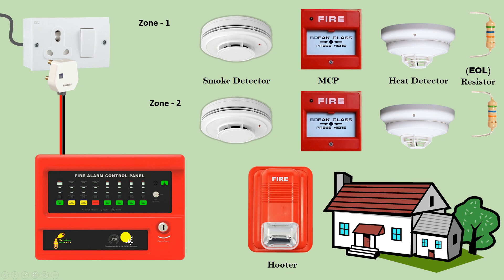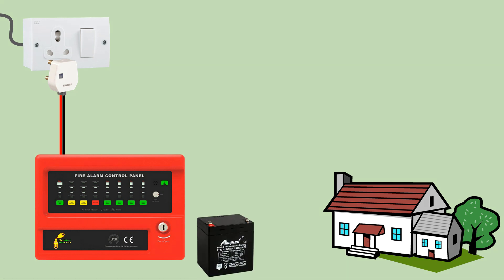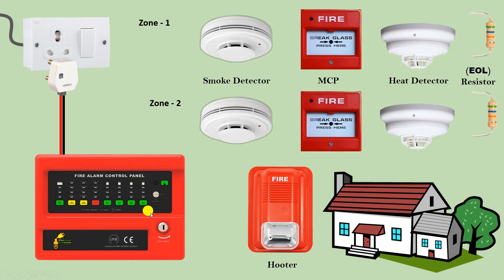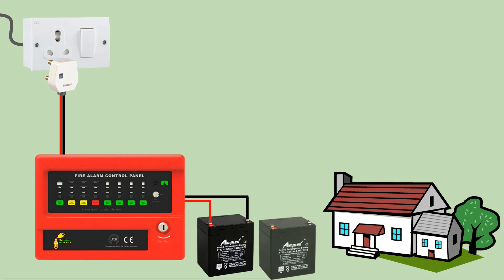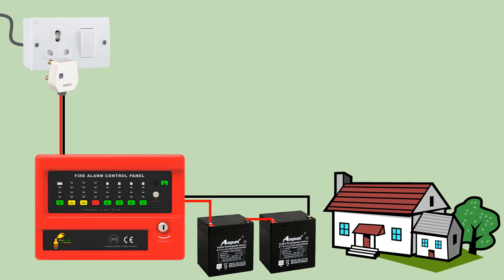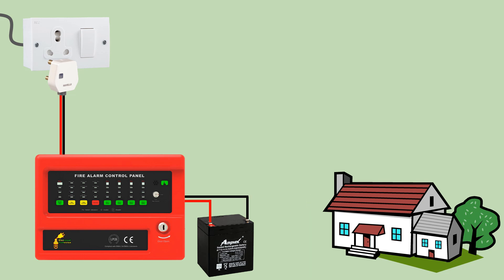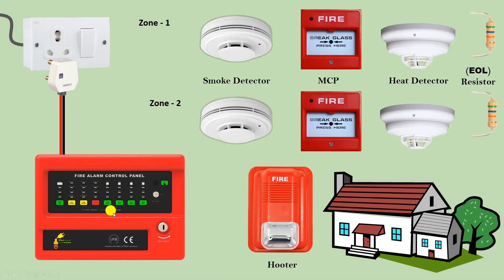Inside the control panel you also have to do a battery connection. Some panels have a small internal battery with two wires — just connect positive and negative. Keep in mind whether the battery is 12 volt or 24 volt. If it is 24 volt you need two batteries; if it is 12 volt you use a single battery.